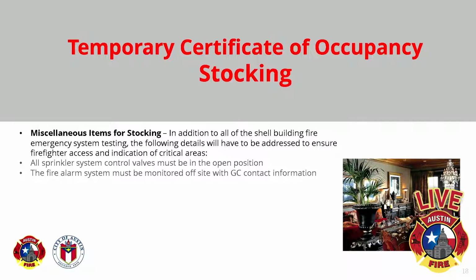Fire alarm systems must be monitored off-site with general contractor contact information. Unless you've got a building engineer already on site, the general contractor is going to be the point of contact for any alarm activations, whether they be general alarms or supervisory alarms. And if you work something out with your alarm tech that they're going to be that point of contact, that's fine too. I just want to know that when the alarm goes off, somebody that knows what's going on is being contacted.